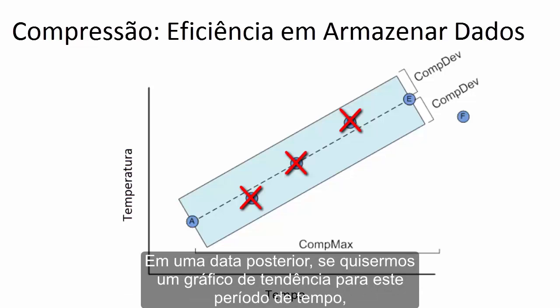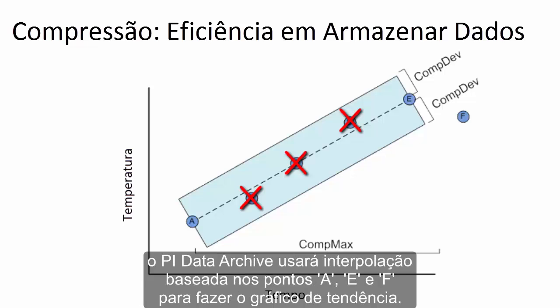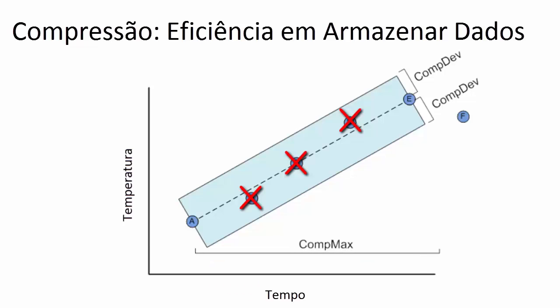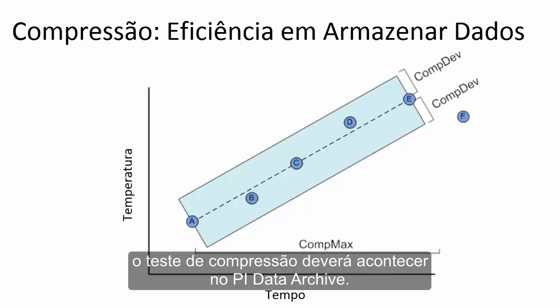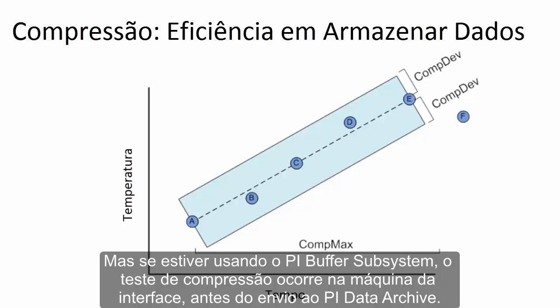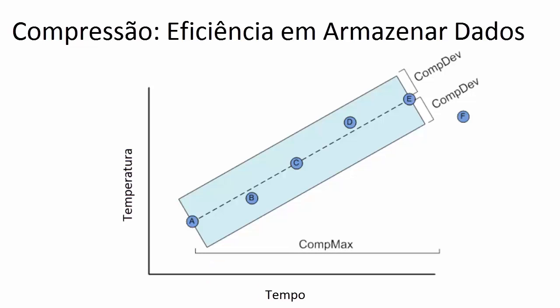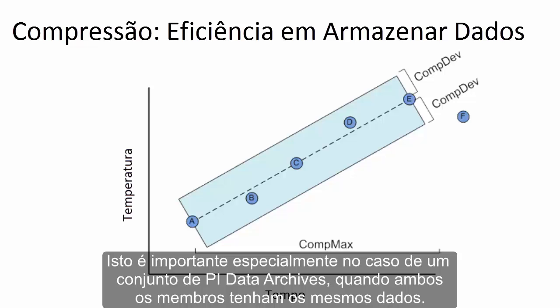At a later date, if we want a PI Trend for this time range, PI Data Archive is going to utilize interpolation based upon points A, E, and F to report the PI Trend. Unless you are using PI Buffer subsystem on the PI Interface node to buffer data, compression testing happens on the PI Data Archive. But if you are using PI Buffer subsystem, then compression testing is performed on the PI Interface node before it is sent to the PI Data Archive. This is especially important for PI Data Archive collectives so that both members of the collective have the same data.